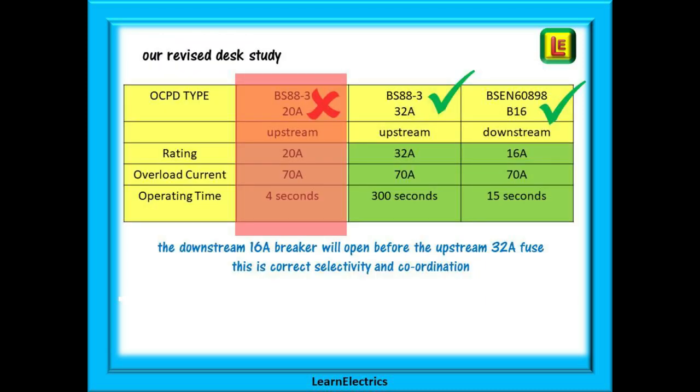Putting this answer into the table we can see that the 32 amp fuse takes 300 seconds to blow but the MCB takes only 15 seconds to operate. Therefore the MCB will operate first, the fault current will disappear from the circuit and the 32 amp fuse will not blow. This means that the cellar sockets will be isolated but the cellar lights will stay on. This is correct selectivity and coordination.